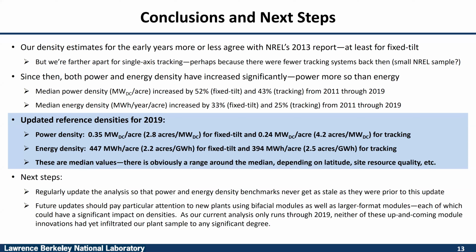Someone asked whether we foresee a continued increase in the power and energy density over the next several years. I guess I'm more optimistic on energy density than power density. For bifacial modules, all else being equal, it may not impact your power density to any great extent, but with added production from the backside, that could theoretically boost your energy density going forward.